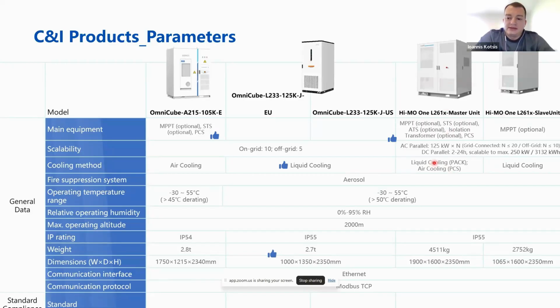Here you can see some of the optionals. We are going to talk about them again later. We can have MPPT to connect the PV panels directly without the inverter if we want, so we have DC coupling. We can have ATS, so it can work with a diesel generator for backup. We can have an STS, for less than 20 milliseconds off-grid operation if we want this. This comes with the isolation transformer, which also fits inside the cabinet. So in this solution, everything is inside the cabinet. No need to add extra equipment. You can see it weighs 4.5 tons, and the slave unit is 2.5.